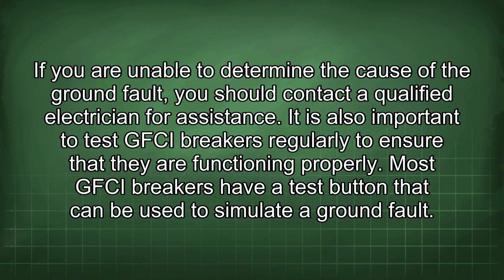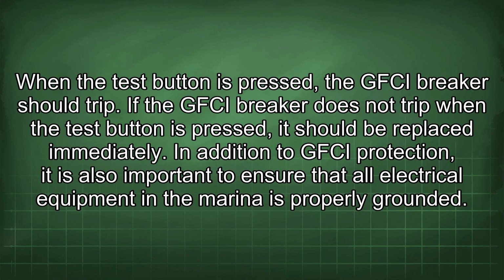It is also important to test GFCI breakers regularly to ensure that they are functioning properly. Most GFCI breakers have a test button that can be used to simulate a ground fault. When the test button is pressed, the GFCI breaker should trip. If the GFCI breaker does not trip when the test button is pressed, it should be replaced immediately.